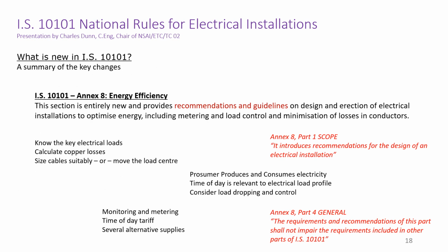Energy efficiency has been relegated to Annex 8 at the back of IS 10101. This is a new departure for IEC and CENELEC. Energy efficiency and carbon footprint is a hot topic across the globe. Electrical installations are in focus as the distributors of energy, and hence they have an effect on carbon footprint. There is some debate as to whether energy efficiency should be included at all in the wiring rules, as the scope of the rules is, you will recall, the safety of electrical installations.